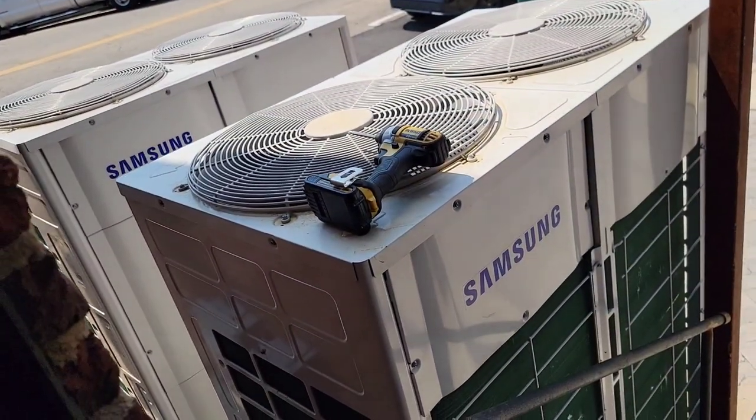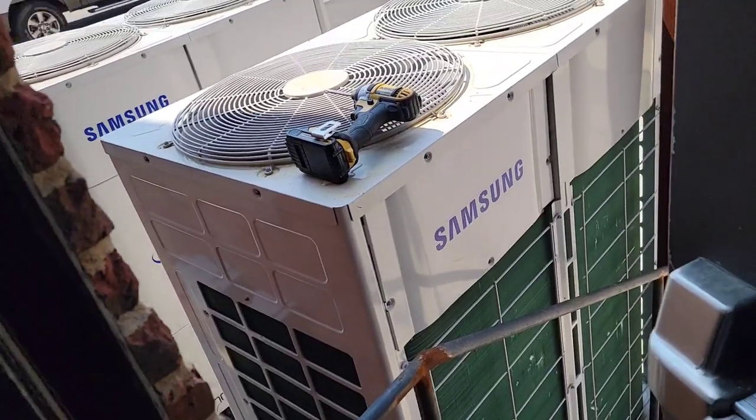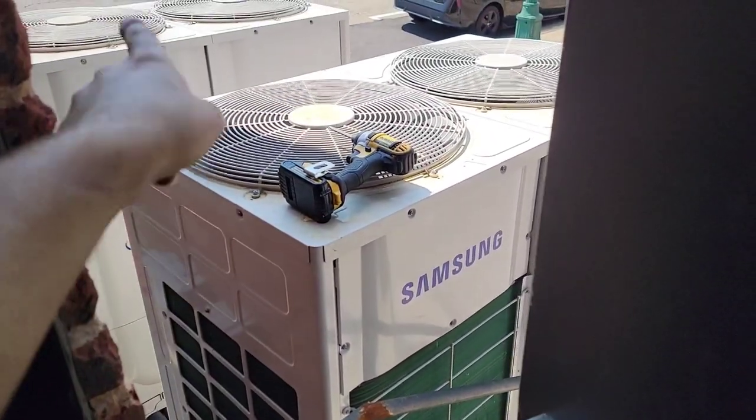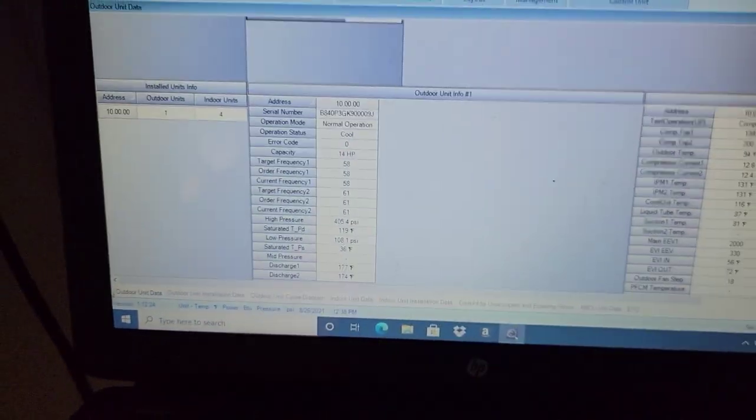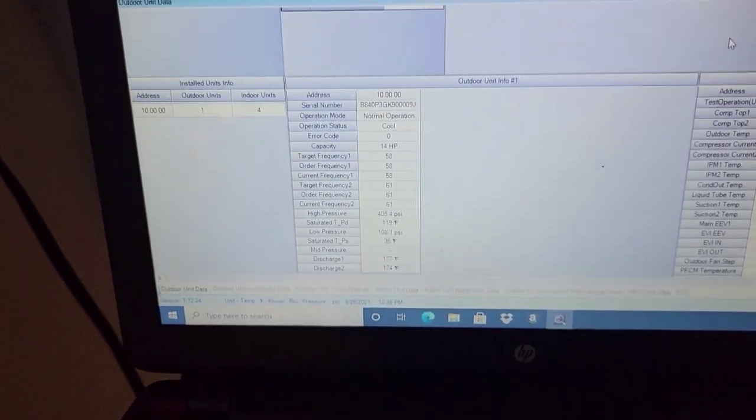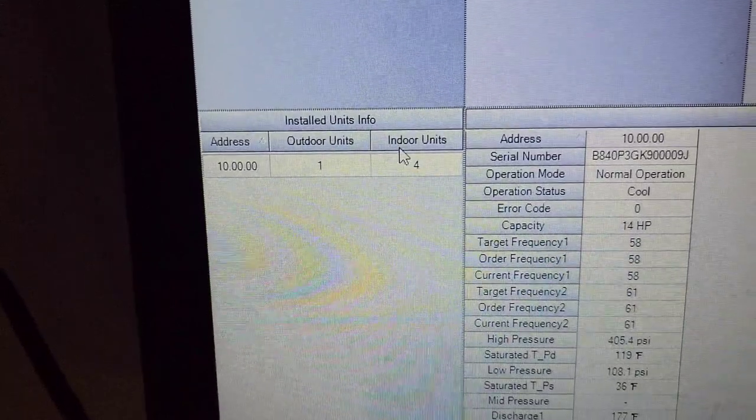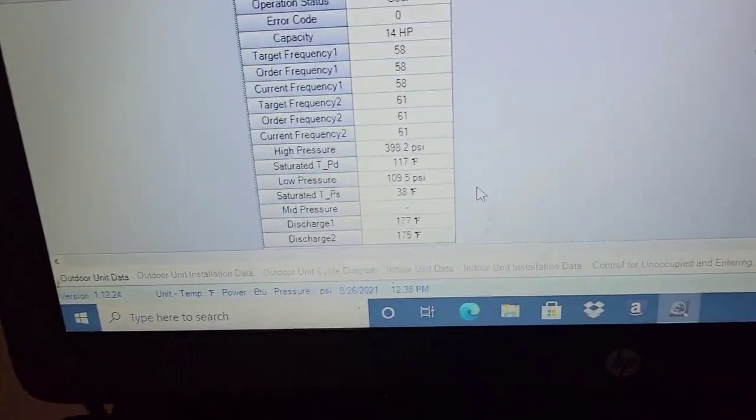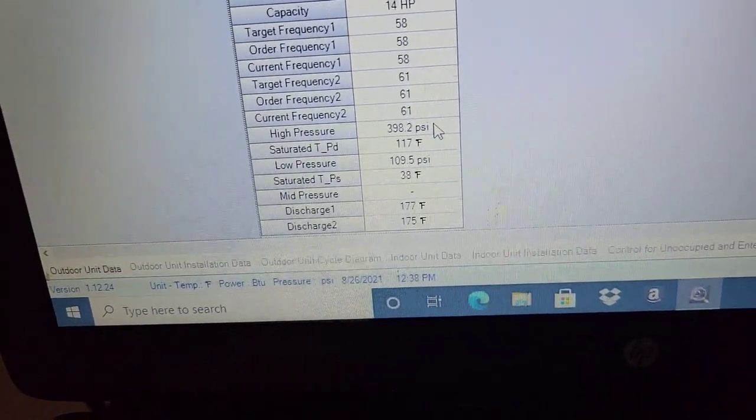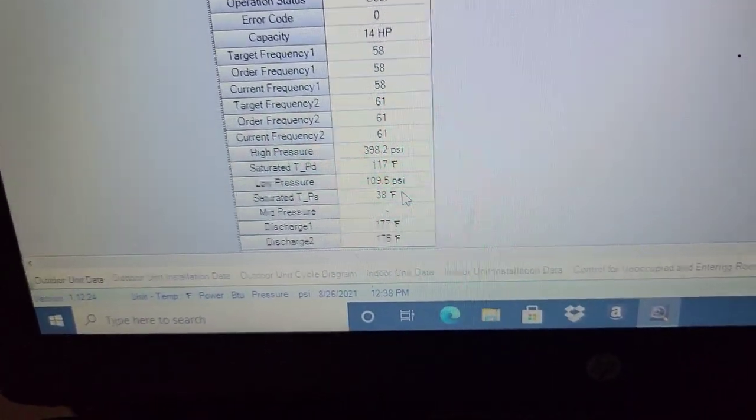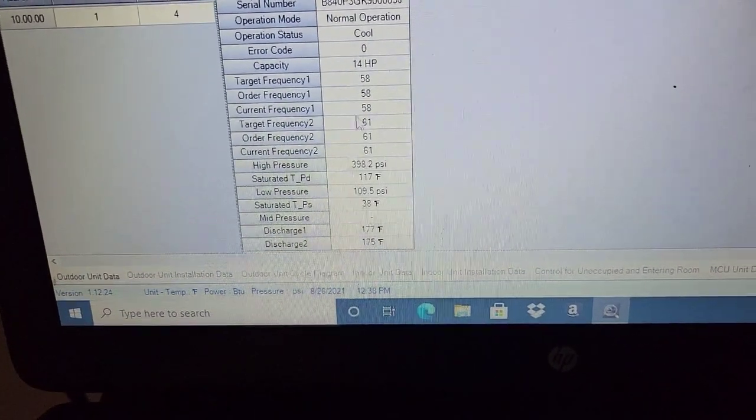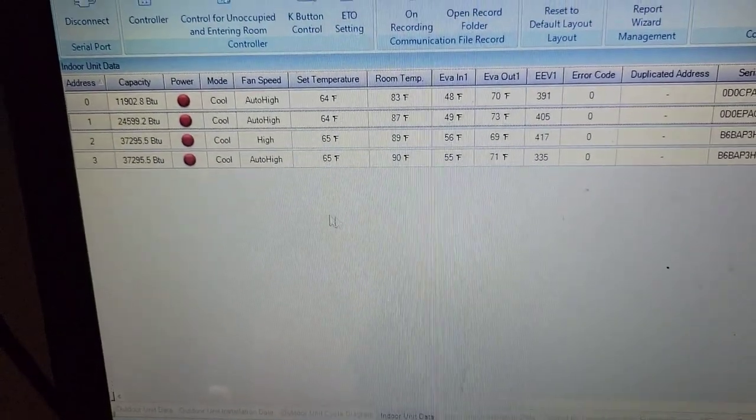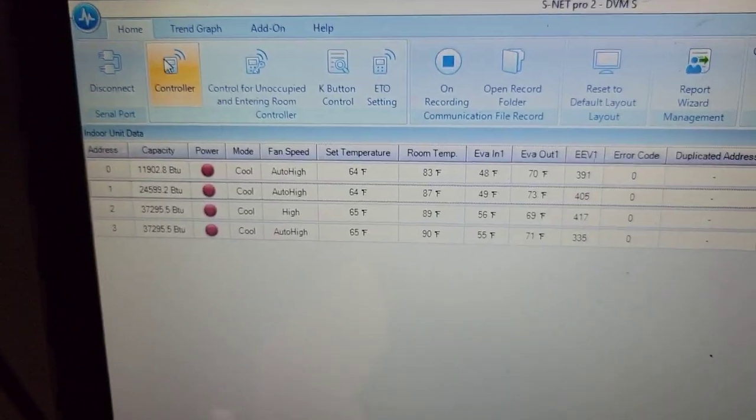Got two DVM condensers right here and one unit handles three indoor units and the other unit handles four indoor units. Right now I'm using my S net pro two to do a little commission. You can see right there, one outdoor unit and four indoor units. If I go down here, you can look at my pressures, high sides 398, low sides 109. It's really hot in here, but we can check out all that information for the outdoor unit and then go to all the indoor units. I've got them all set to cool via the controller.